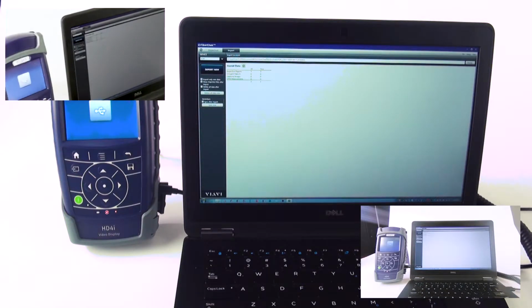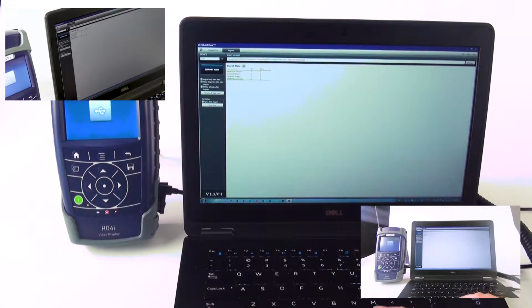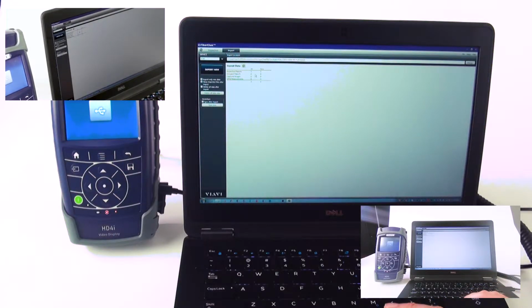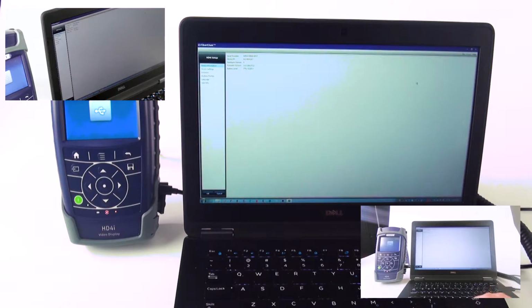What I want to do now is plug in my HD4i display, and you'll notice that the screen of the HD4i just changed to a USB icon, and it tells me information about what's on this device. I have 3 inspection reports that are saved, and that's it. But what I want to do is go in and set up my pass-fail profiles in here. So if I choose Setup HD4i, there's a number of options available on the left. Device information, device settings. I can even update my firmware in here. This is currently up to date.